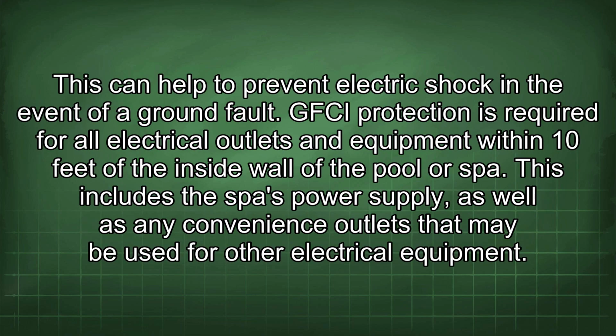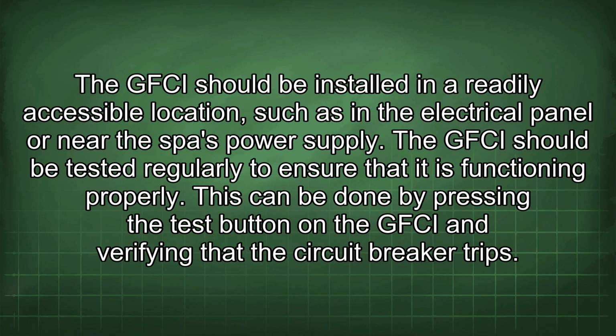This can help to prevent electric shock in the event of a ground fault. GFCI protection is required for all electrical outlets and equipment within 10 feet of the inside wall of the pool or SPA. This includes the SPA's power supply, as well as any convenience outlets that may be used for other electrical equipment. The GFCI should be installed in a readily accessible location, such as an electrical panel or near the SPA's power supply. The GFCI should be tested regularly to ensure that it is functioning properly. This can be done by pressing the test button on the GFCI and verifying that the circuit breaker trips.